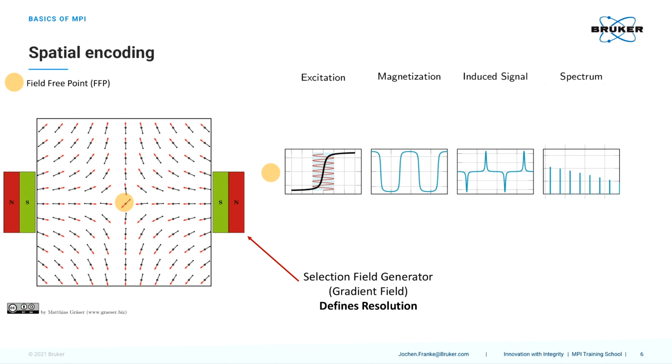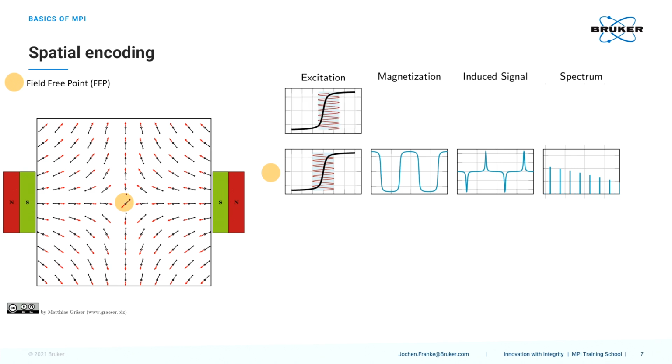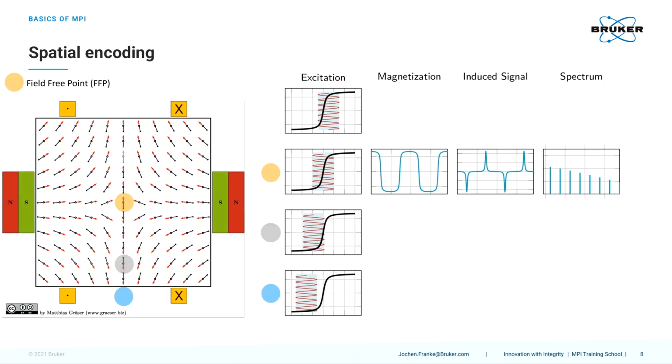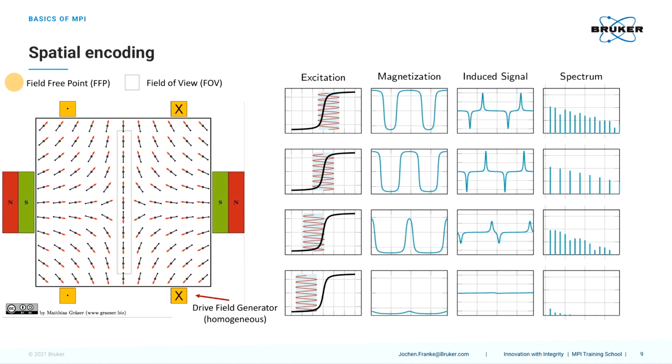Okay. Now, with having an oscillating magnetic field, and the particles located here, we are driving through this magnetization curve in a centered way, and therefore the magnetization is also kind of centered. If we have particles away from the origin of the field-free point, we drive through the magnetization curve of the particles non-symmetrically, and therefore the magnetization response over time looks different according to their position. And exactly this is what we are exploiting for image reconstruction.